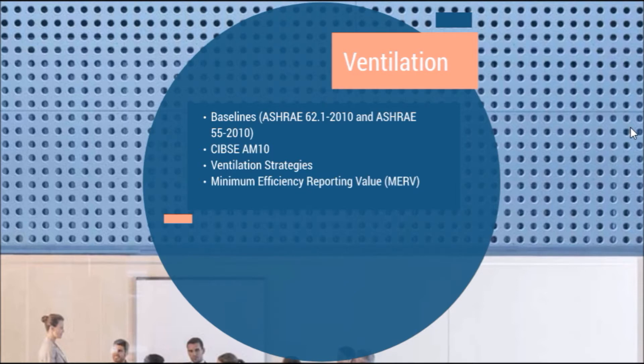The main theme is that CO2, smoke, dust, chemicals, volatile organic compounds, and off-gassing are all hazards to building occupants that can be decreased through proper ventilation. Higher ventilation through a proper HVAC system means cleaner air. We also have the Minimum Efficiency Reporting Value, or MERV — basically a standard rating for vent filters between 1 and 16, where 16 is the highest. We want our rating to be at least 13.